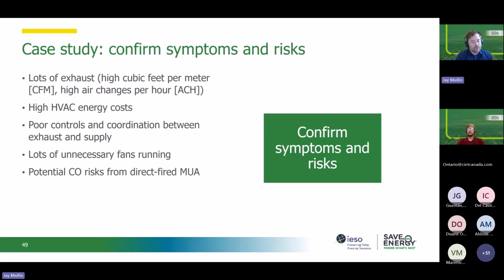They had poor controls and coordination between exhaust and supply. So they had many different exhaust units, many different air supply units happening throughout the facility, and very poor coordination between those. That was leading to a lot of negative pressure symptoms in their facility. So they were experiencing those symptoms. Saw lots of unnecessary fans running, and because of the negative pressure situation, it wasn't verified, but they were worried about potential carbon monoxide risks from direct fired makeup air units, where those combustion products might not be exhausted in the way that they should.